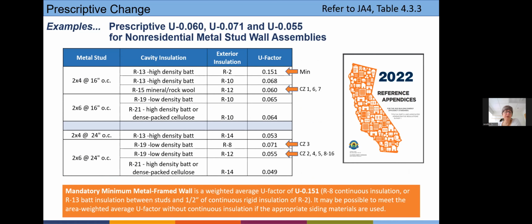What some of these new requirements mean is, essentially for the metal framed walls, the new U factor means you're most likely seeing R13 batt insulation between studs with a half an inch of continuous rigid insulation, for example, or you might see a metal stud that has an R8, which could be about 2 inches of continuous exterior insulation. With computer performance modeling, it's possible to trade off some of that, as long as you're meeting your minimum requirements.